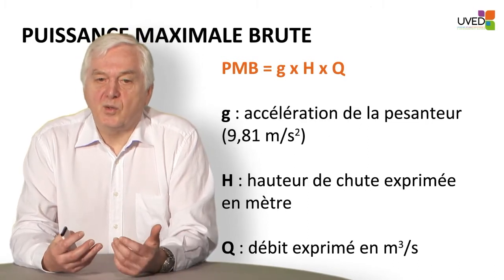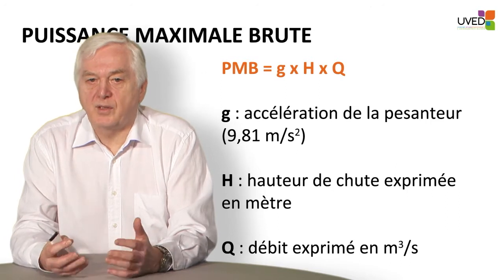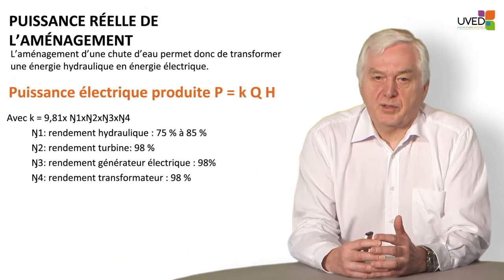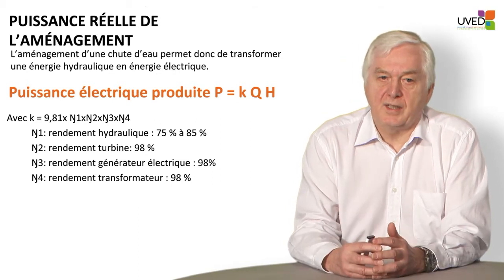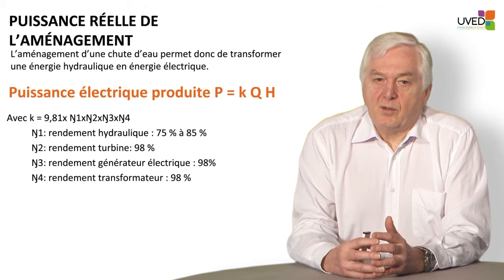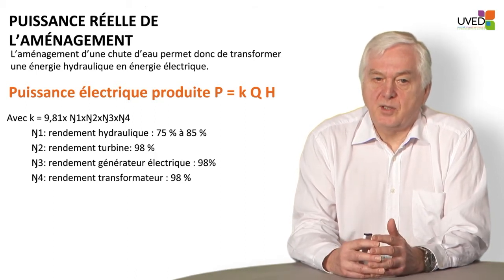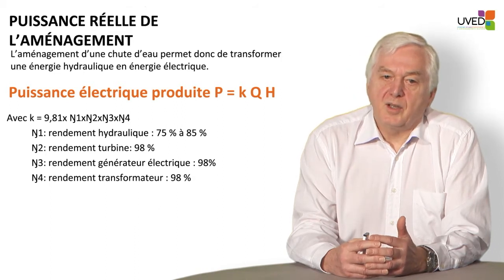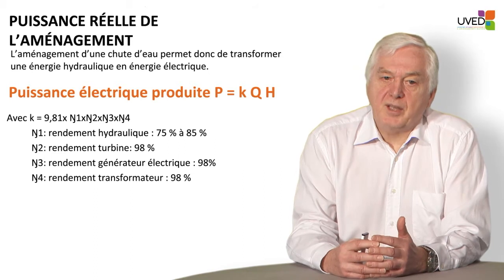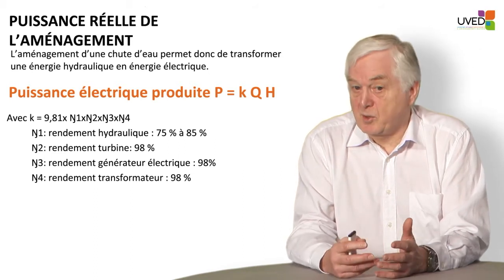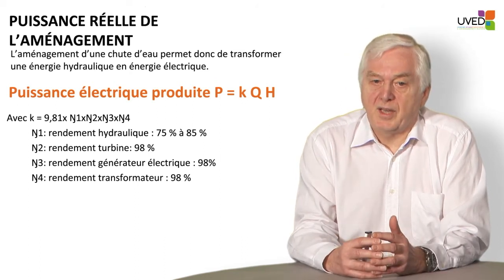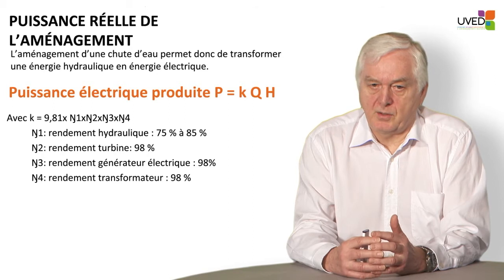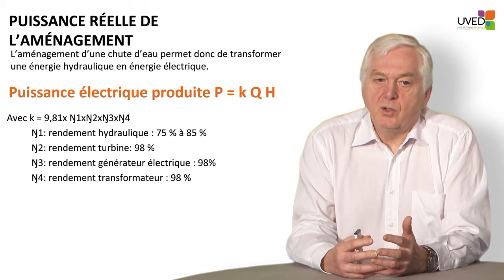Next, we have to make a technical-economic calculation. Intuitively, big flows require bigger investments than small flows. To calculate the real power of the plant, we convert the gross power into electrical power. We feed it through tubes into the turbine, and the passage through the pipelines is where the losses are maximum. Hydraulic yield will be between 75% and 85%. The losses are due to friction between the water and the pipes, and also losses when the water goes through the particular shape of the pipe.